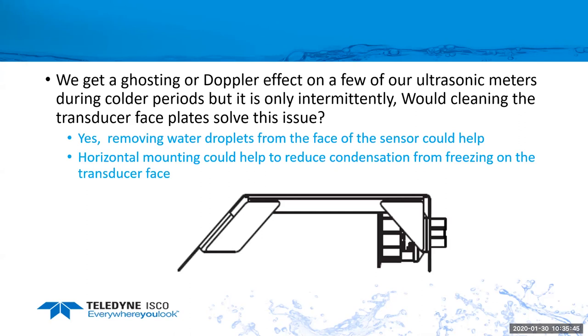All right, now that it's colder out, I've had several questions coming in about cold weather. This person was having problems with ghosting with their ultrasonic sensor when it's cold out. They were asking about cleaning the face of it. So yes, cleaning the water droplets off the face of the sensor could help. If it's mounted in a vertical orientation in colder weather, sometimes we get steam coming up. You get water droplets developing on the face of the ultrasonic transducer. The water droplets can freeze, and then that could cause some problems.